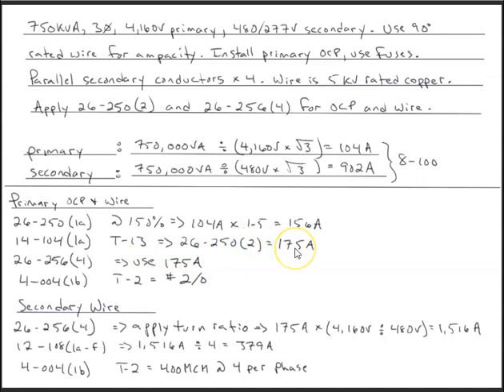So we have our overcurrent protection, 175. We're going to size this accordingly, and we end up here with a number 2/0 wire. For the secondary wire, we're going to take the 175 amps that we've chosen for our overcurrent device, and we're just simply applying the turn ratio of the transformer.